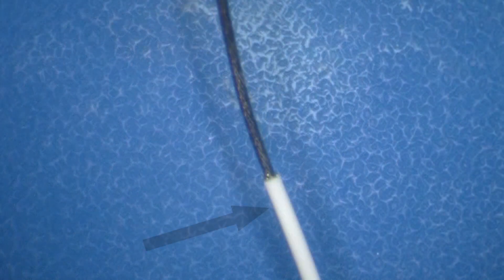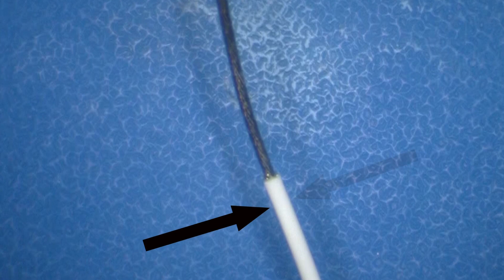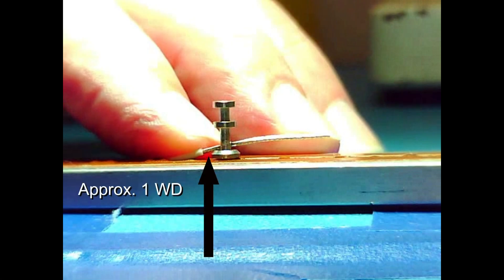A wire diameter is defined as the diameter of the wire conductor and the outer diameter of the insulation. Place the wire in contact with the terminal, leaving approximately one wire diameter from the insulation cut end to the point where the soldered connection will begin.